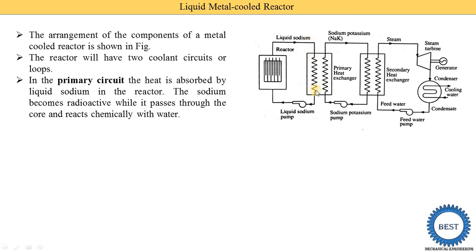In the primary heat exchanger, liquid sodium transfers its heat energy to sodium-potassium alloy. This heated sodium-potassium is then supplied to the secondary heat exchanger, where it transfers heat energy to feed water, converting it into steam. This steam is supplied to the steam turbine, where steam energy is converted to mechanical energy, which drives the generator to produce electrical energy. Exhaust steam from the turbine goes to the condenser, where it is condensed back to water, and the cycle continues.